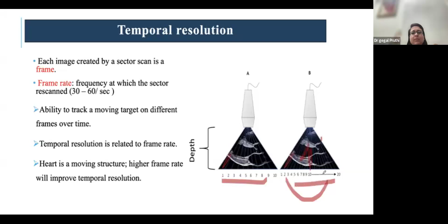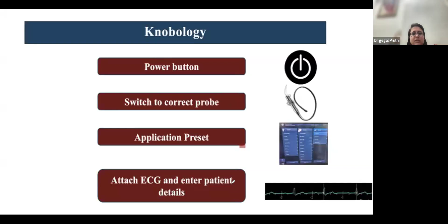Now you have turned the power button on and switched to the correct probe. Each transducer will have a different list of application presets based on frequency and footprint that will automatically select the ideal frequency, depth, and gain for that application. Application preset is similar to selecting your day mode and night mode on your phone camera. Now, after power button on, switch to the correct probe, and application preset done, you have to attach the ECG and enter the patient details so that you can save your images and the videos.